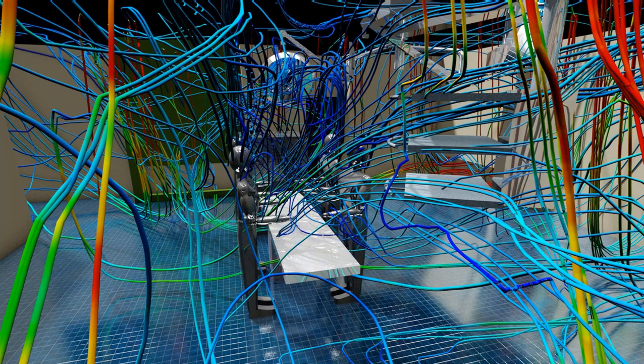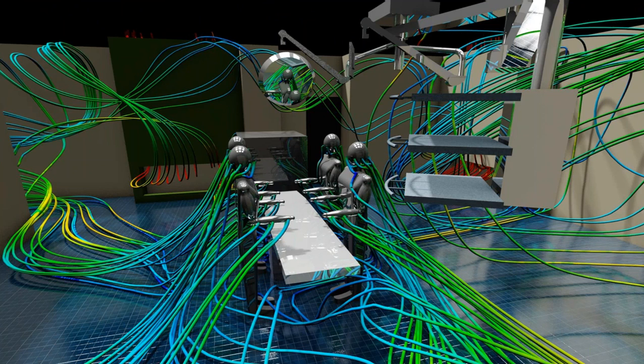Something like 1 million people get secondary infections every year in the US alone as a result of going into hospital and having some kind of surgery. Sadly, 100,000 people die. It costs the healthcare industry something like $33 billion. So a design change was made, and in actual fact, a big plenum was installed in the ceiling, and it created a much more laminar airflow. And here we can see now that the streamlines and the air is not circulating or recirculating. It's being carried nicely away through to the ventilation system.